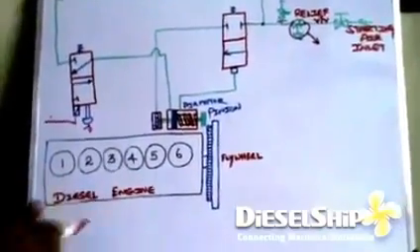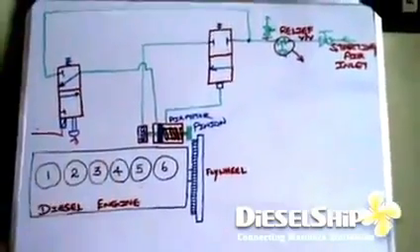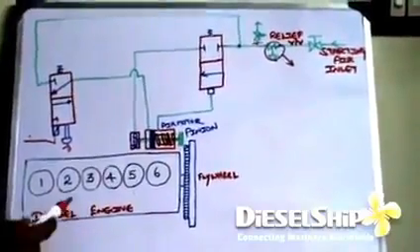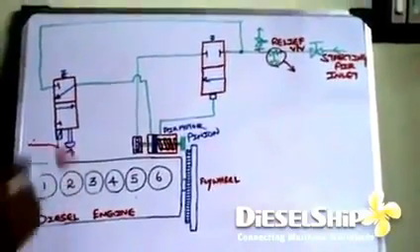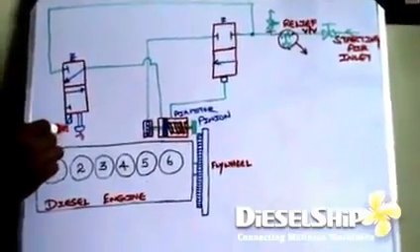Thus the pinion is engaged with the help of the piston, and with the help of the vanes and air pusher, the engine is turned. And as the engine picks up speed and starts combustion, let's say at 30 or 40 RPM depending on the engine design, it fires on fuel now. So a signal from the governor or from the control system, depending on the design, comes and deactivates the solenoid valve.